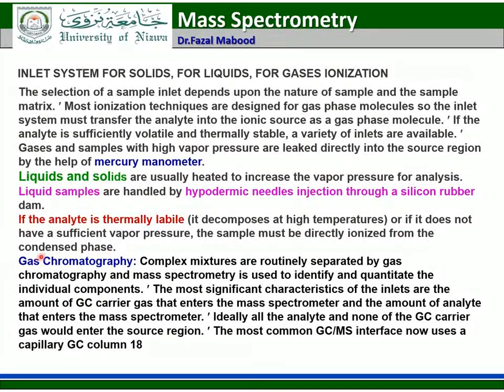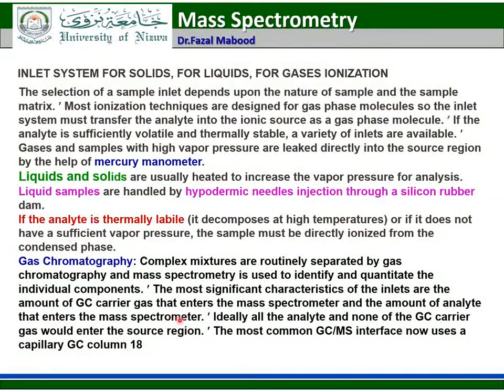Complex mixtures are routinely separated by gas chromatography and mass spectrometry is used to identify and quantify the individual components. The most significant characteristic of the inlets is the amount of GC carrier gas and the amount of analyte that enter the mass spectrometer. Ideally, all the analyte and none of the GC carrier gas would enter the source region. The most common GC-MS interface now uses a capillary GC column.